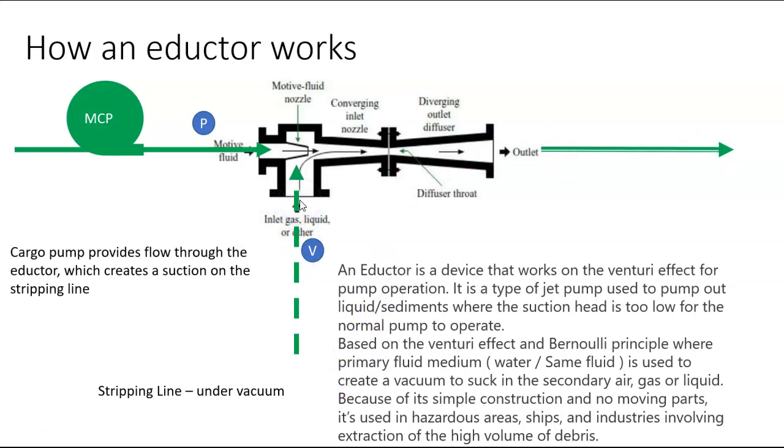And you say, well, what the hell's the sense of that? Why not just use the pump? Well, when we start running out of product, when we get down to the bottom, and the pump is not really filled up with any kind of volume of liquid anymore, it needs to have that volume. The centrifugal pump needs to be full. I'm going to use the term fat, dumb, and happy all the time. If you can keep that pump impeller full, it's going to pump all day long.